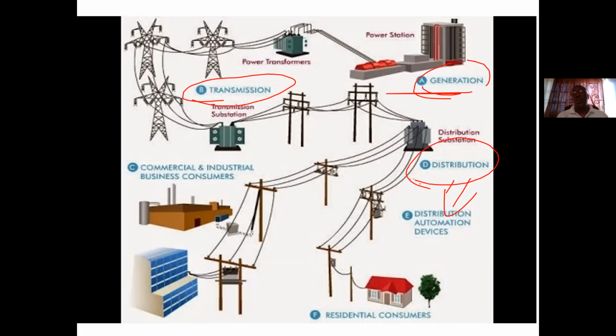At the generation level, generators produce electricity at relatively low voltage as far as a power system is concerned. We're going anywhere from the region of 13.8 kilovolts, that's at the generator terminal, up to 24 kilovolts.